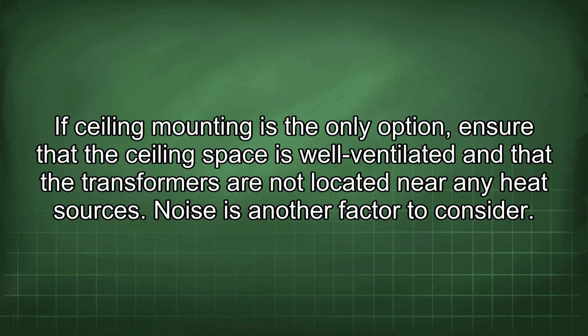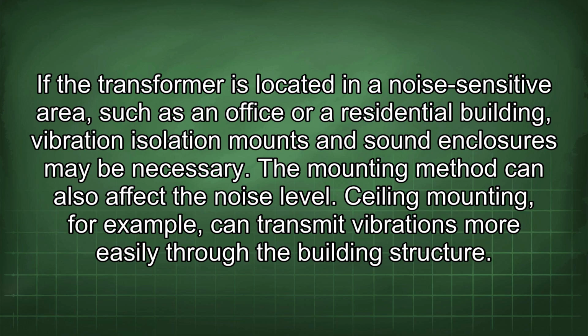If ceiling mounting is the only option, ensure that the ceiling space is well ventilated and that the transformers are not located near any heat sources. Noise is another factor to consider. If the transformer is located in a noise-sensitive area, such as an office or a residential building, vibration isolation mounts and sound enclosures may be necessary. The mounting method can also affect the noise level. Ceiling mounting, for example, can transmit vibrations more easily through the building structure.